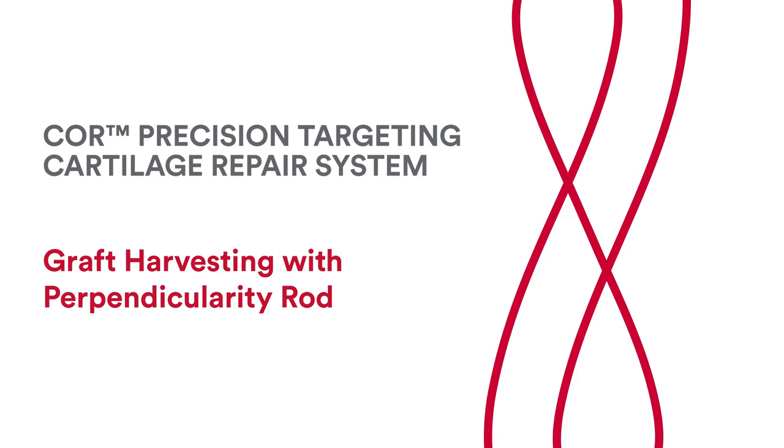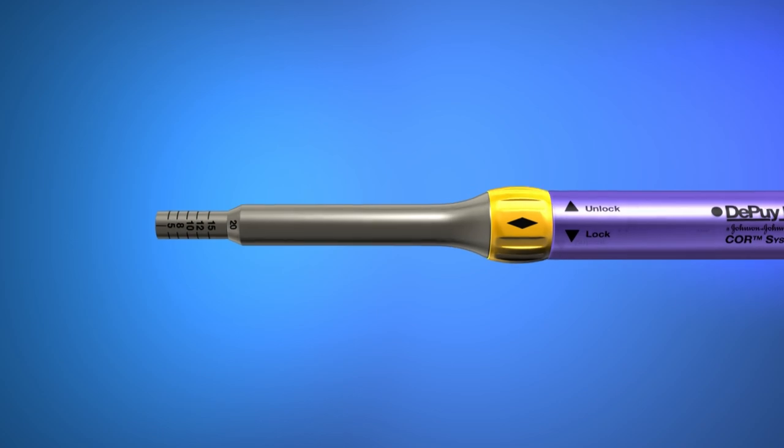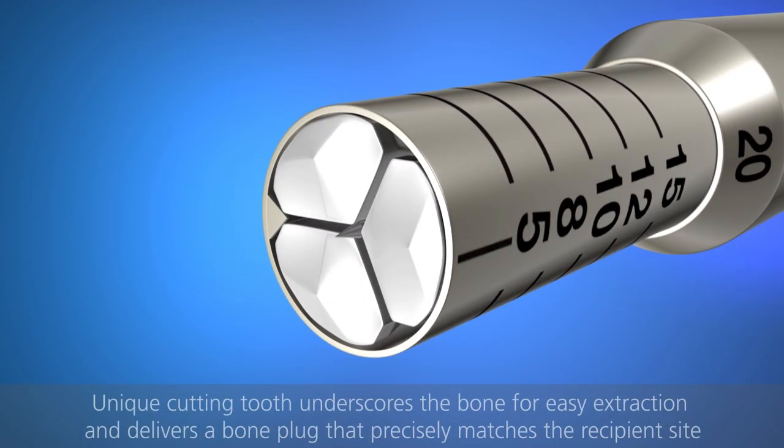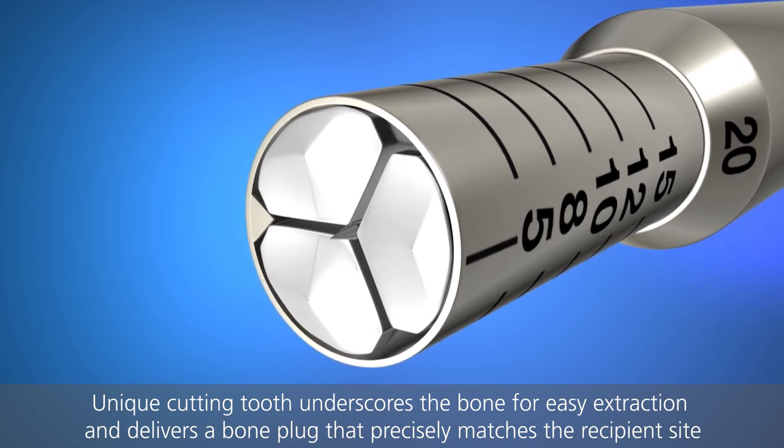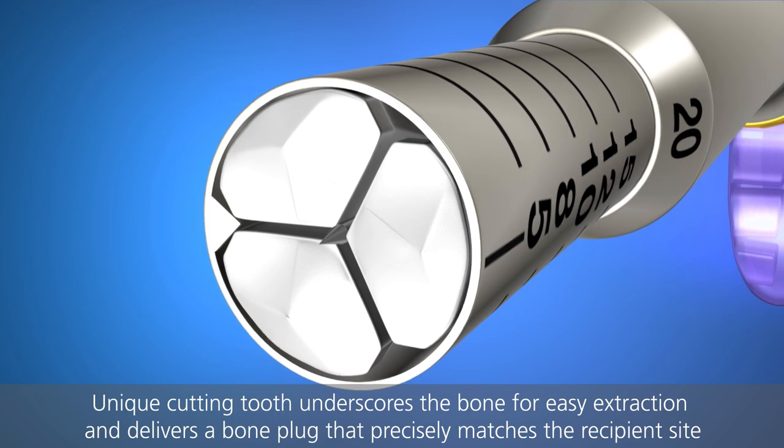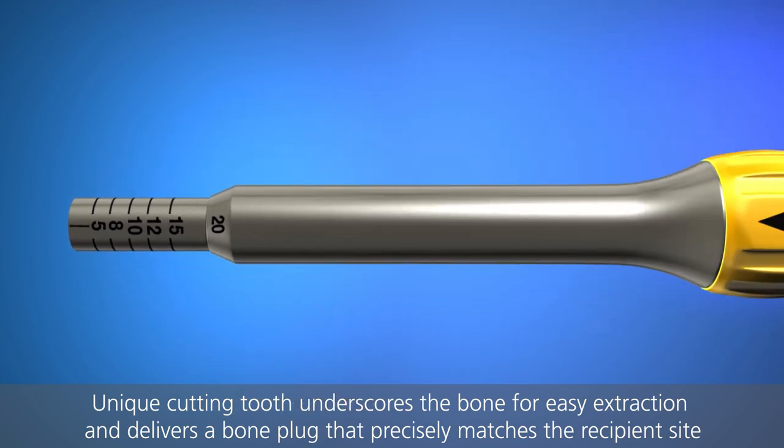Graft harvesting with perpendicularity rod. Prepare for graft harvesting by inserting the perpendicularity rod into the distal end of the harvester delivery guide or cutter. The rod is properly seated when it engages with the cutting tooth on the harvester cutter. The cutting tooth, a unique feature of the COR system, underscores the cancellous bone at the distal end of the harvester tube and allows for a precise depth cut.